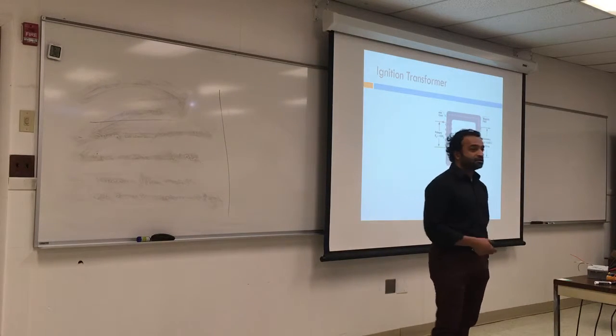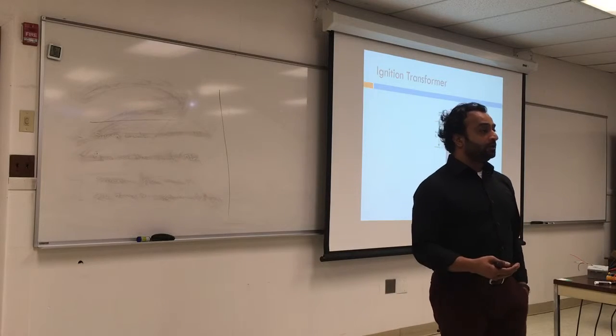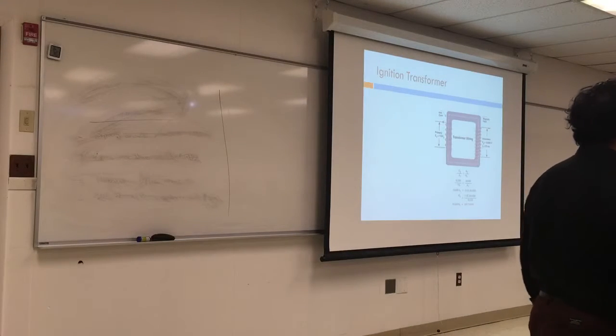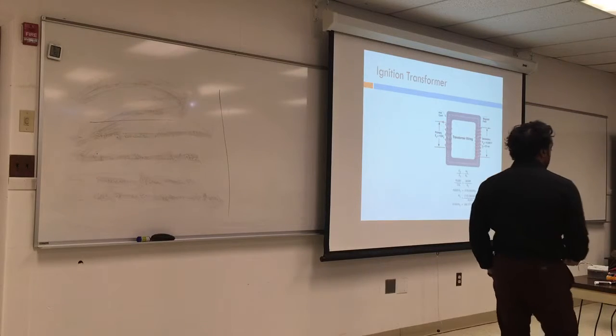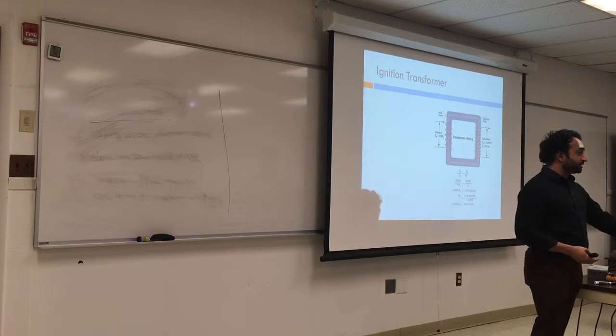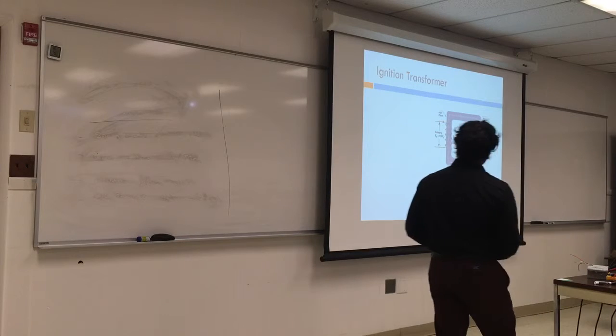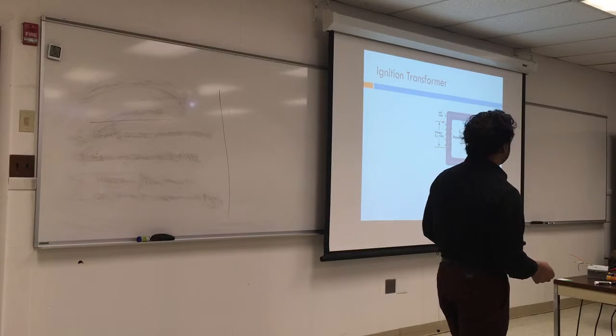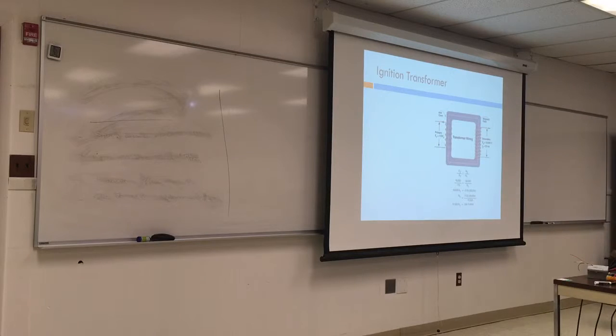Transformers, we talked about that. Transformers either step up the voltage or step it down. We step it up to 10,000 volts. In this case here it is 14,000 volts, so that's a lot of volts coming in. You don't have to worry about the calculation here, but what you want to know is what is the primary and what is the secondary. The primary is the input. So what you put in is the primary. Secondary is what comes out of it. Is it reversible? Not always. So do not assume that you can put in 24 volts and get 120 volts.